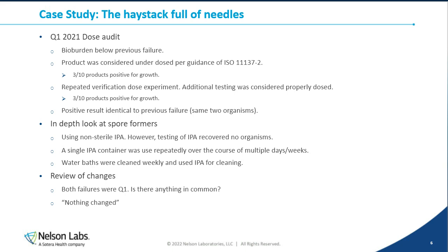We repeated the verification dose experiment because it was underdosed. That is allowable. And that one was dosed properly and within what is considered the acceptable dose range. However, we once again had 3 out of 10 positives for the test of sterility. When we had the positives identified, this is where things got a little bit interesting: we recovered pretty much the exact same organisms we had seen during the previous failure. So that told us it wasn't really an issue with dosing or sample prep. It's probably more so we have an ongoing issue that we haven't truly addressed. So we need to look deeper. We need to look into this.